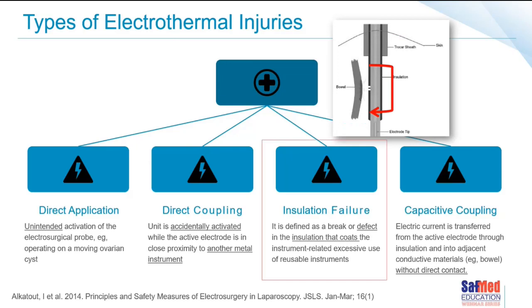Now, insulation failure is the main cause of laparoscopic electrosurgical injuries, and of course it's associated with an instrument that is used repeatedly. Because of that repeated use, you have breakdown of some form of the insulation that coats the outside of the actual instrument. By lowering the concentration of current used, the risk of accidental burns can actually be reduced. 18% of the insulation defects are along the instrument in an area that's outside of the view of the monitor, but distal to the protective cannula of the port itself.